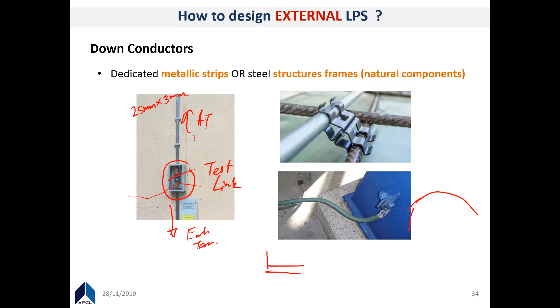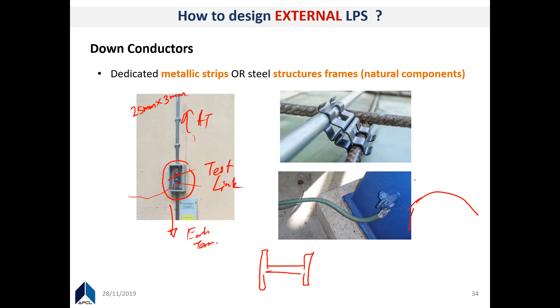This is from a steel column. You might have seen certain structures having I channels, I profiles, I sections, being used for columns. You can use these same columns, but with proper bonding at the air termination and also at the earth termination, as down conductors themselves. But you still have to be aware of what sort of services you are connecting your electrical and electronic earthing to the structures, and if you're mounting them, you also have to be careful of touch potentials.